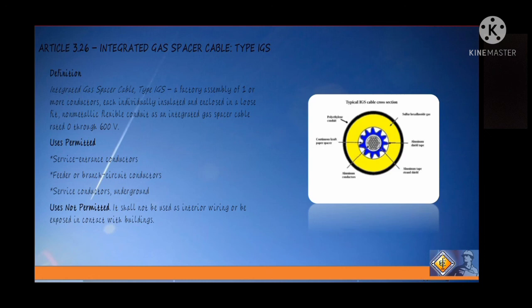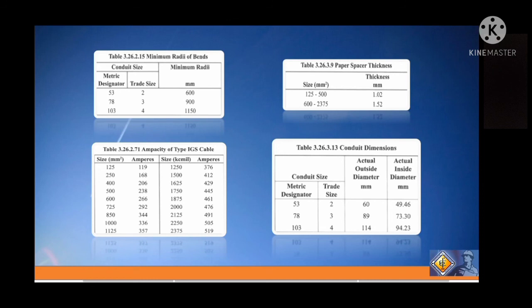So yung itsura ng ating type IGS na makikita natin sa right side ng ating slide, and yung kanyang mga components. So pagdating naman sa uses permitted niya, it is used in service entrance conductors, feeder or branch circuit conductors, service conductors, underground. So uses not permitted, it shall not be used as interior wiring or be exposed in contact with buildings. So here is the table showing the minimum radius of bends, ampacity of type IGS cable, the paper spacer thickness, and the conduit dimension, which show the size, amperes, and the thickness.